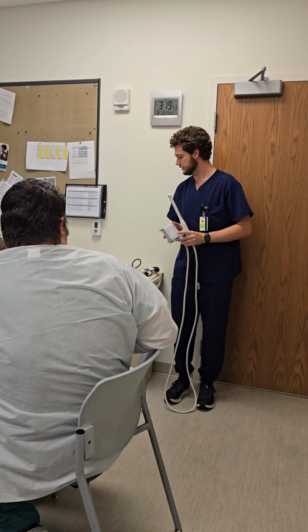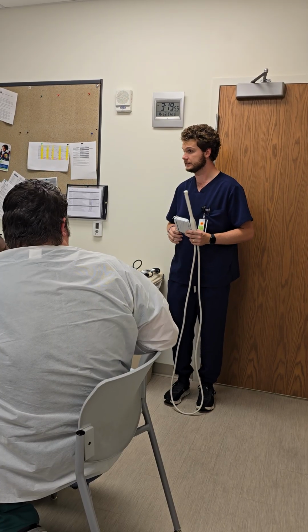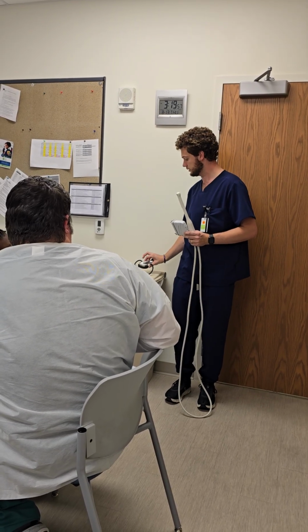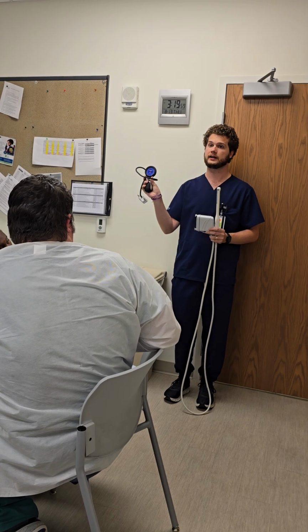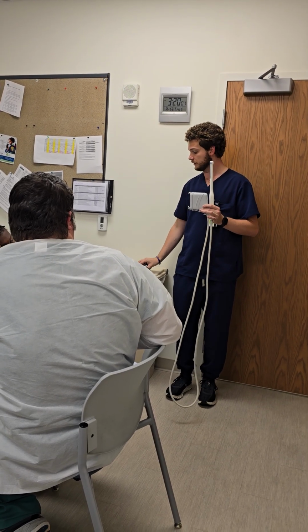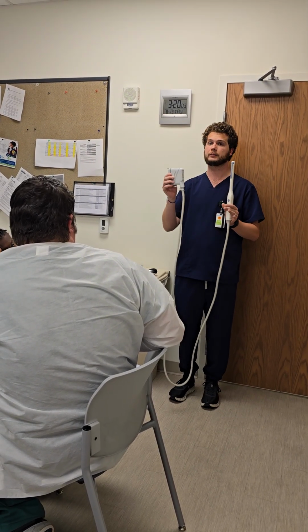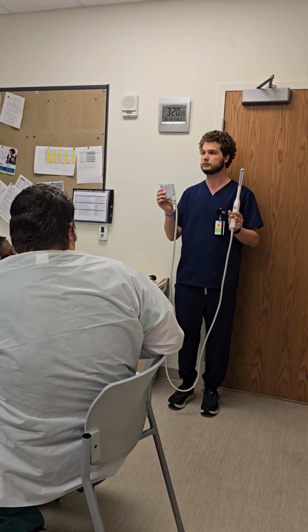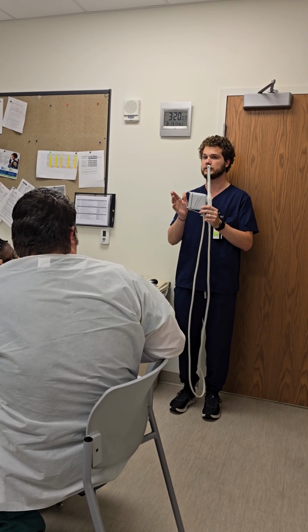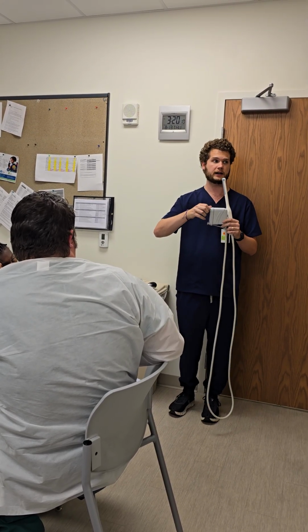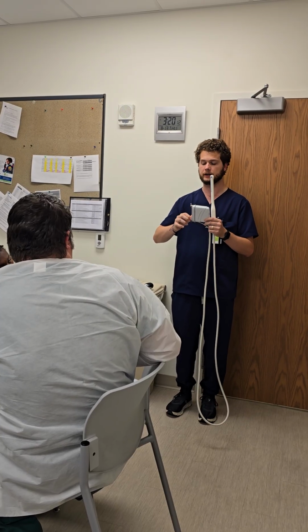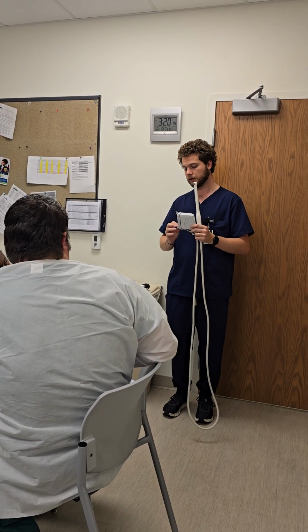First thing we want you to do in decontam when you get it is do a leak test. The leak test, we have a leak tester here. We're going to do a dry test and a wet test. It's going to come to you from the OR with the cap on. It could be sprayed, it could not be sprayed, but the cap should be on when it gets to you. Go ahead and take the cap off all the way. It's just a screw cap. And we're going to do the pressure test.